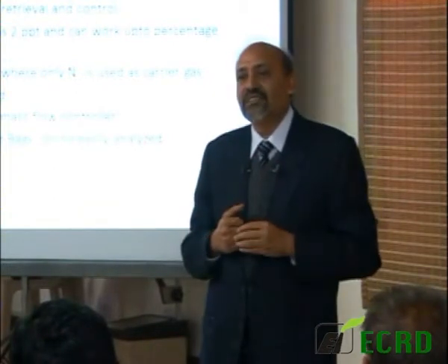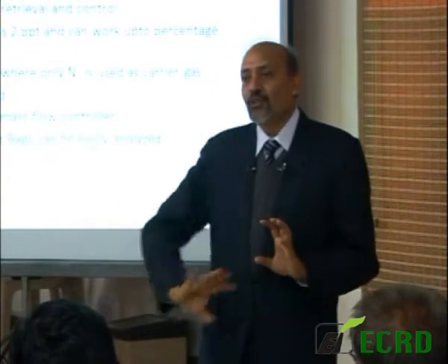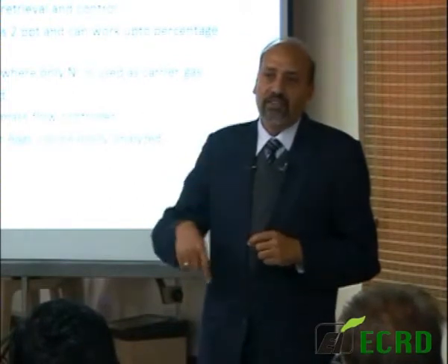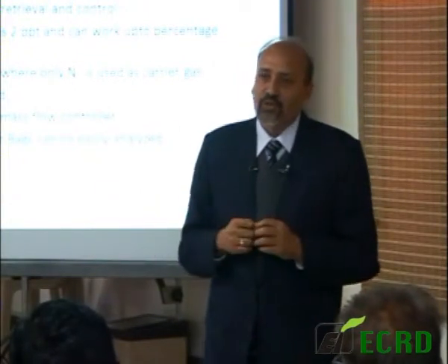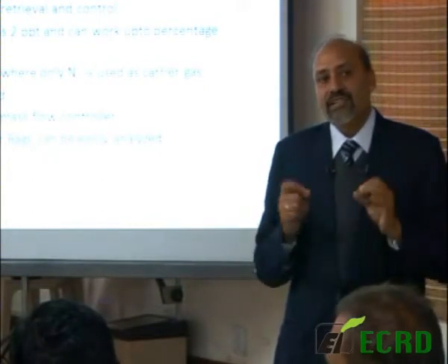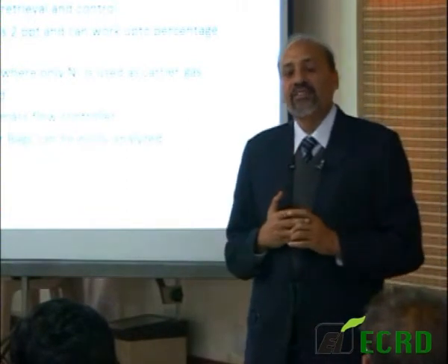So they've taken an industrial PC, they've embedded the PC inside the GC, combined the two into one small neat compact box, and they've handed over all the control functions of the GC to the PC. So the software controls the GC operation in terms of the flow rate or the temperature rise of the column or the traps and so on. Everything is controlled by the PC software, which is embedded inside the GC itself. It is still a capillary column GC, which they very nicely integrated to a PC, those two together into one box. The third thing that they've introduced into that system is an automatic sampler.